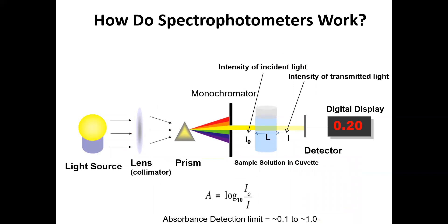How does the spectrophotometer work? You have the machine, and this is all invisible within it. There is a light source — a white light. The light shines on a lens, also called the collimator, which condenses the light towards the prism. The prism converts white light into different colors. Then the monochromator allows one specific color to pass through a slit with a specific diameter for that color.